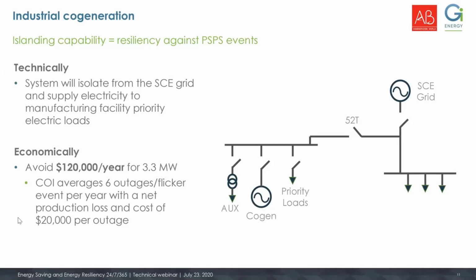Technically, what we do when we install an island-capable cogen is split the load of the customer or facility in two. We need to understand with the customer which are priority loads at the facility that need to keep running during an outage, and which loads are not needed during such an event. If needed, we can consider the entire facility a priority load, but we obviously need to think of cost. What we do is split those priority and non-priority loads with an automatic switch.